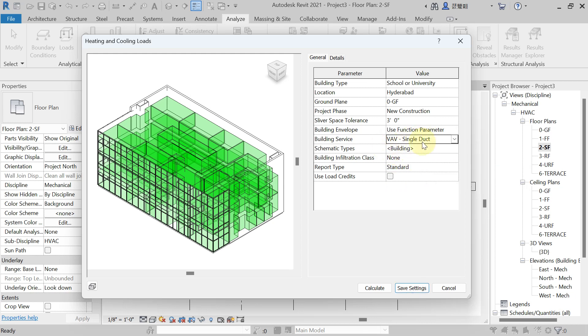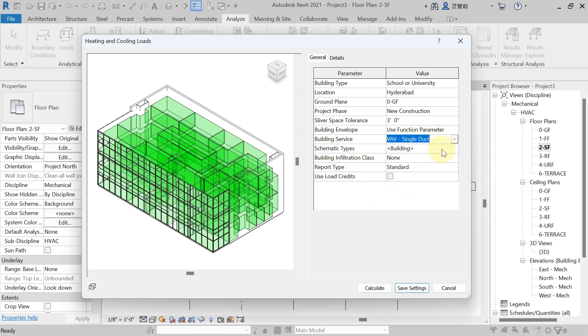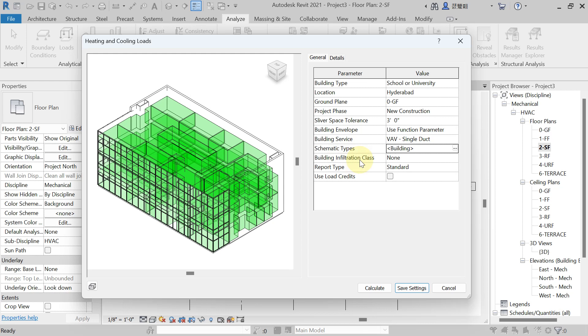Single Duct means you are using one duct to supply conditioned air to each space. If you need to supply hot air to some rooms and cold air to others, you use a double duct — in that case select VAV Dual Duct. For Schematic Type, leave it at the default 'Building.' For Building Infiltration Class — which defines the air leakage rate — I am selecting Medium. The Report Type is Standard.